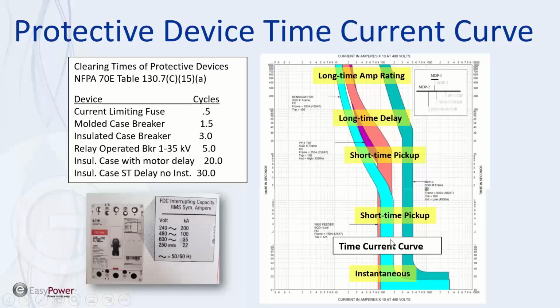And then down at the bottom it says instantaneous area. That would be for short circuits and ground faults. So that's a very, very quick amount of time with a fairly high amount of current, depending on what your system is. So again, you can have equipment like this breaker right here. It's not a 10,000 amp breaker. At 240 volts, it's 200,000 amps. So it's got a very high rating, and you're not going to get this at Home Depot. You'd have to get this at an electrical supply store.